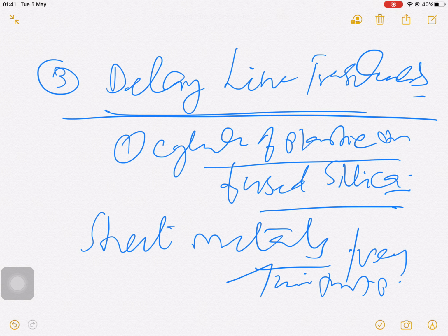A delay line is often used as a thermal insulator, protecting the heat sensitive transducer element from direct contact with the hot test piece. A delay line can also be shaped or contoured to improve the sound coupling in sharply curved or confined spaces. Okay. Fourth type is the immersion transducer.